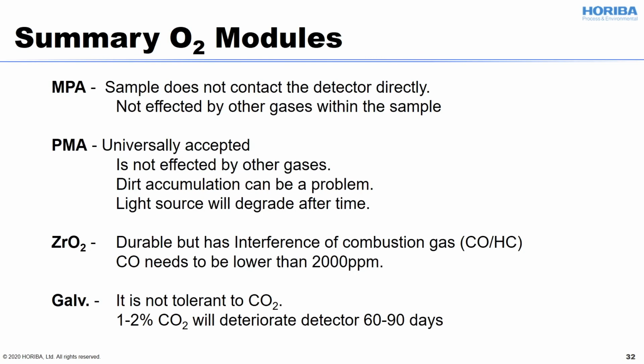The galvanic method is the lowest cost and works with a battery, which requires you to replace it about every year. It is not tolerant to CO2, and CO2 will deteriorate the detector. But it is still low cost to run.